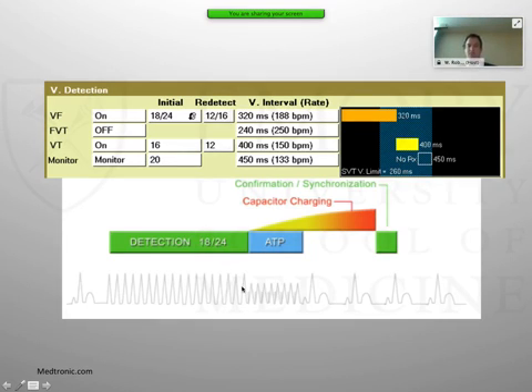This slide didn't come through very well, but once it has determined that ventricular tachycardia is occurring, it will typically deliver a burst of antitachycardia pacing. So it will pace slightly faster than the rhythm while the device is charging. That does not delay therapy. And then once it's charged, it takes a quick peek back at the rhythm to say, is this still happening or has it terminated while I was charging? And then it will deliver a shock.